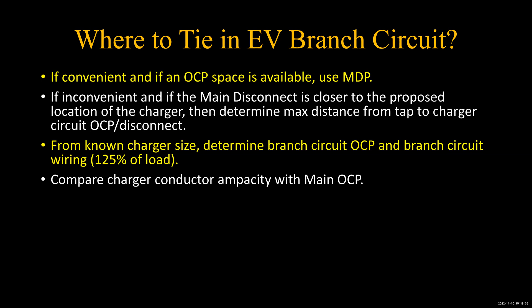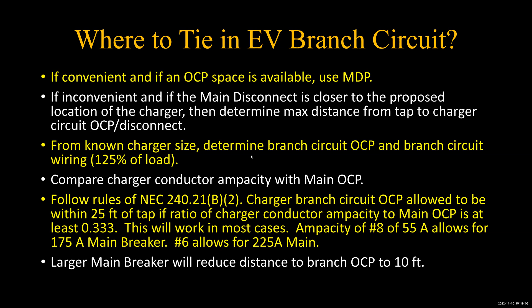Compare your charger conductor ampacity with the main circuit overcurrent protection. And then you follow 240.21(B)(2). And it all depends on whether you're doing a 25-foot tap or whether you're using a 10-foot tap. But that tells you how big your wires have to be. And if you have a larger main breaker, then you're probably going to have to reduce the distance to the overcurrent protection to 10 feet, because otherwise you're going to have to use too big of a wire, maybe a whole lot bigger than you would normally need for that size circuit to charge your car.